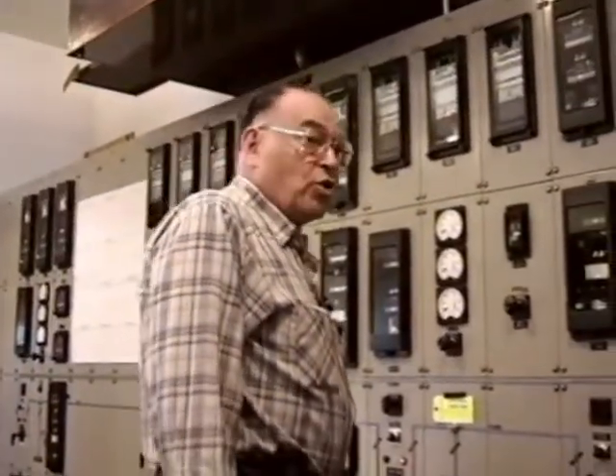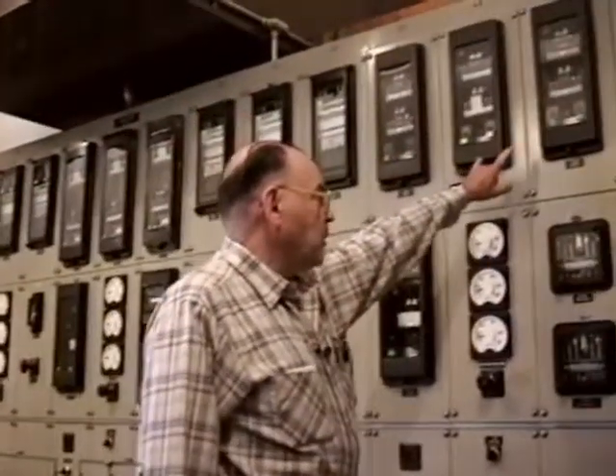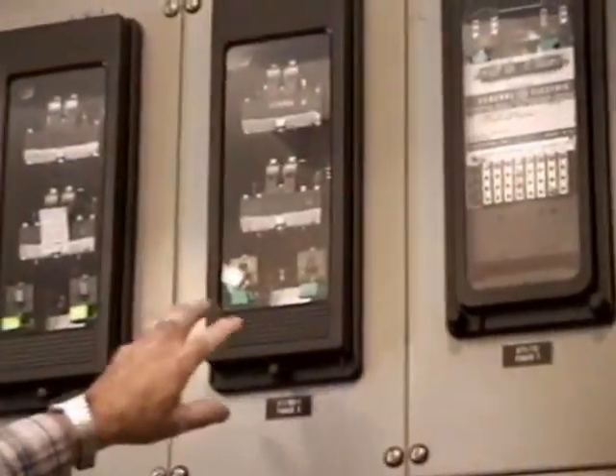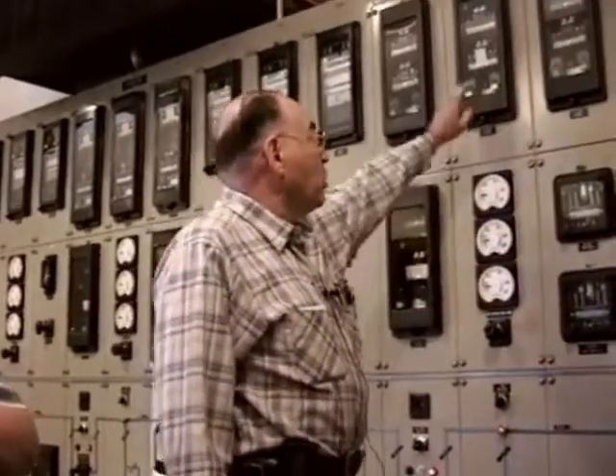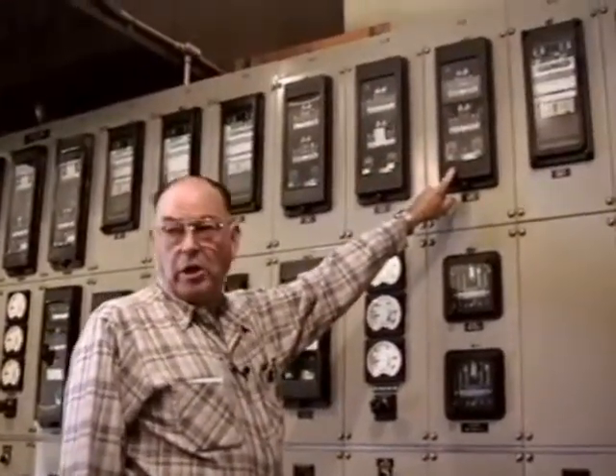Something else that might be of interest is our relaying equipment, which is our line protection and station protection equipment. If something happens out here, like a tree branch falling in, or like a few years ago when a cat got up in the bus work out here and fried itself, we have to have some means of taking that section of the station or the line off the system.